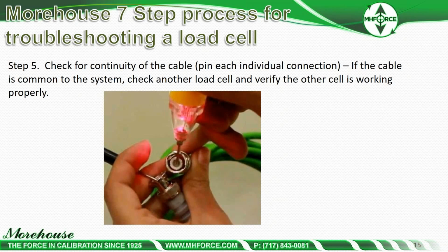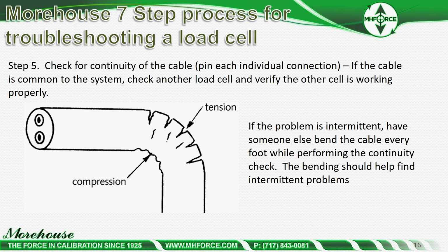And if we're pointed back to the cable, the next step, or a continuation of step 5, is to pin each individual connection. And while you're pinning it, I recommend bending it. So if you have an intermittent problem, which is the worst type of problem, if you're pinning the cable and you can bend it every foot or every 6 inches, you're going to see it eventually in the meter. It's going to show open line, and when it shows open, you know that's what the problem is, that it's an intermittent connection.